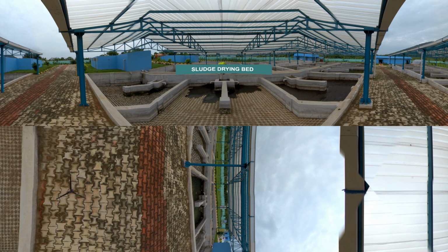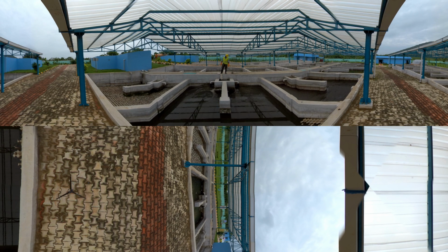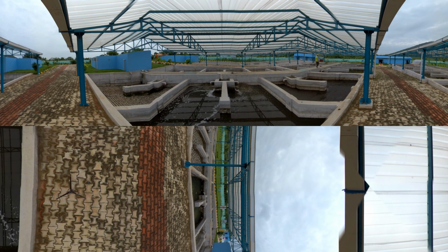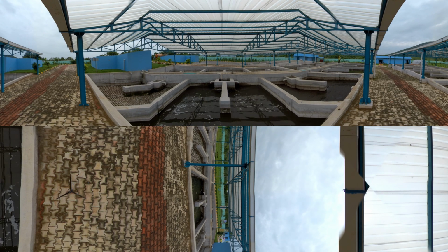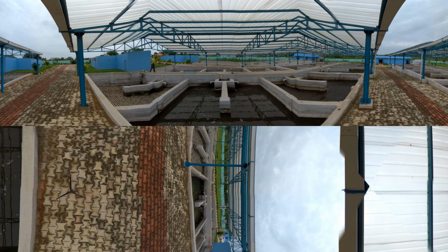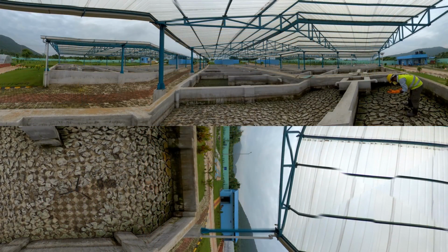Sludge drying bed. The solids in the form of slurry from the third chamber of the stabilization reactor are pumped to sludge drying beds. These are shallow tanks with a tapering concrete bottom filled with filter media, sand and gravel with a perforated pipe at the bottom to collect percolating liquid. The sludge in the sludge drying bed undergoes solid-liquid separation and the liquid flows to collection tank 1, from where it is sent to ISAF for further treatment. Operation.